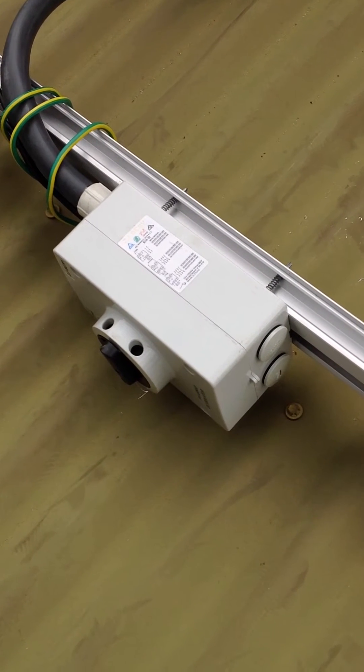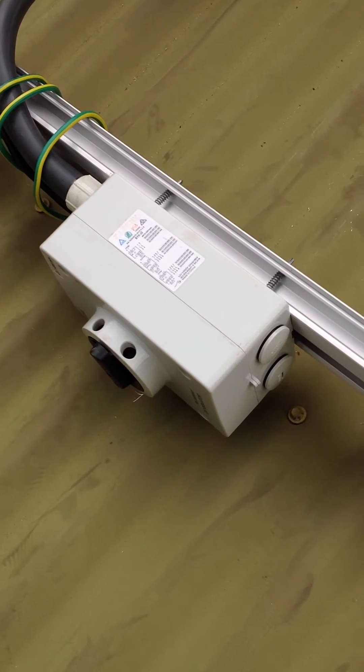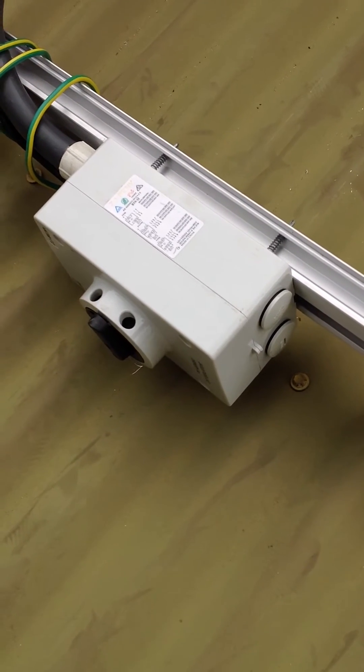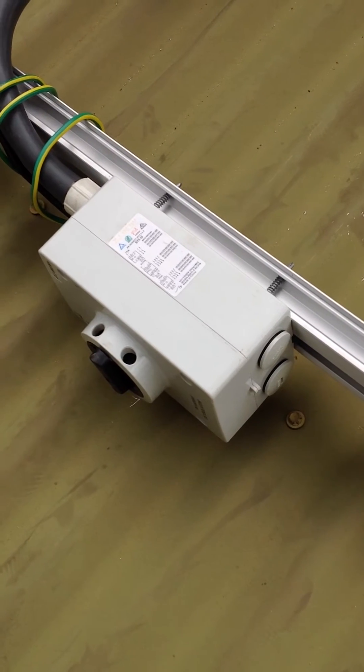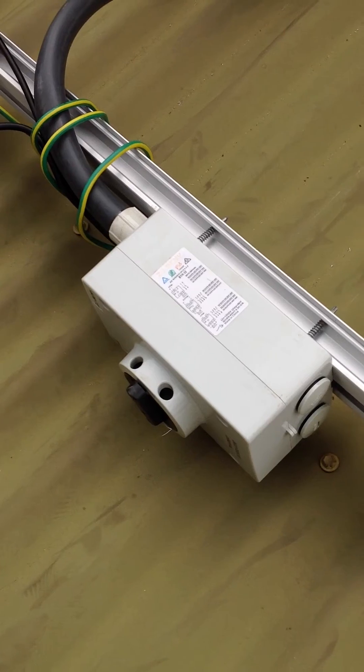Now, AS5033 says the isolator must be accessible. So from the side of the last panel, we've been allowing no more than 100 to 150mm, so someone can easily come up to the roof and isolate.